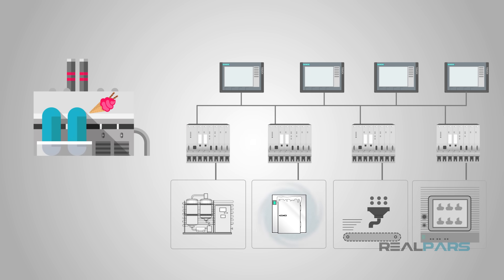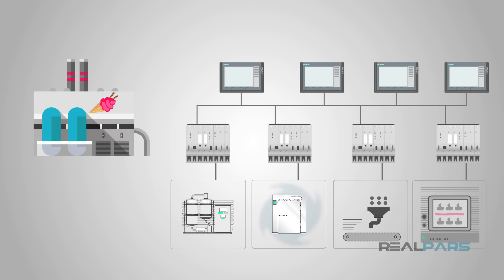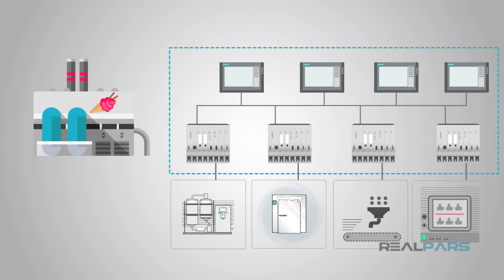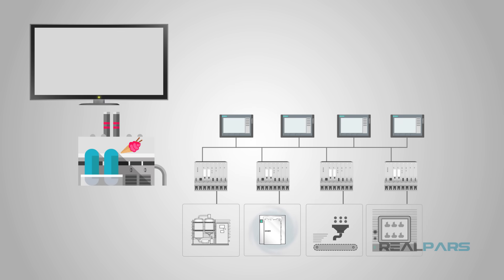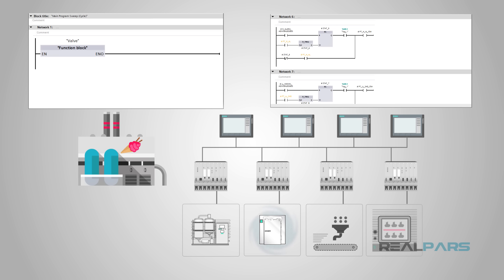The DCS was really good at autonomously controlling single or multiple processes. Another major benefit of the DCS was the integrated monitoring and control system, similar to today's SCADA systems — the entire tag base is already created for the process control and available to use on the monitoring and control screens. The DCS has also had function block programming, which is a section or several lines of code behind a single interface. That interface may handle the manual and automatic operation of a valve, saving a lot of time and redundant programming.